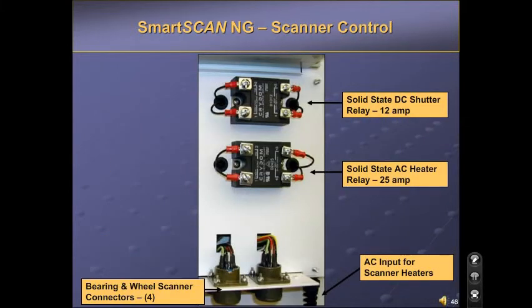Whether the system you are working with has 2 or 4 scanners, bearing and hot wheel, all of the shutters and heaters are controlled by two heavy-duty solid-state relays. The top relay is DC and controls the shutters. The bottom relay is AC and controls the heaters. The heaters are set up on a timed cycle from the processor that we discussed earlier. The cycle will vary by the reading received from the temperature probe. The scanner connectors are mounted to the bottom of the chassis.